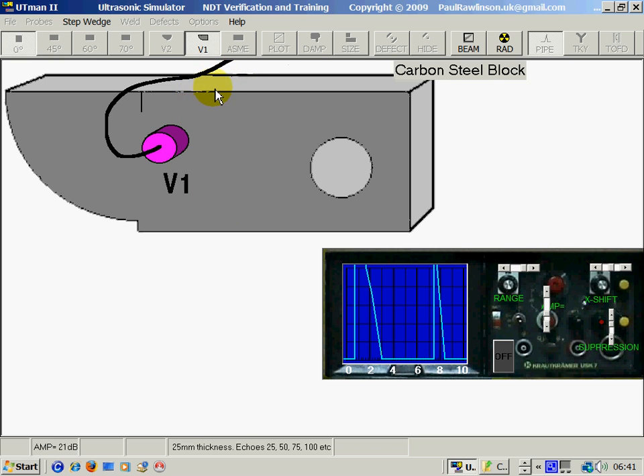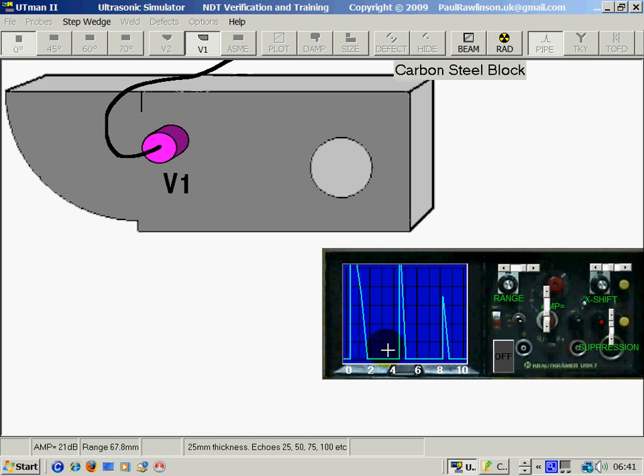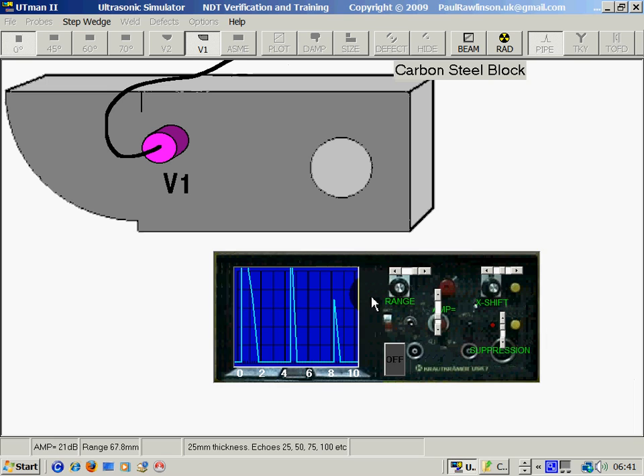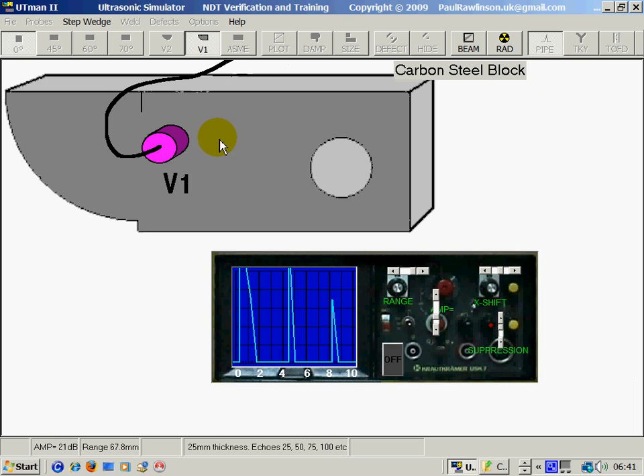The sound is going through the block which is 25mm and echoing inside there. So we get multiple echoes on the A scan here of the back wall of this 25mm V1 block.